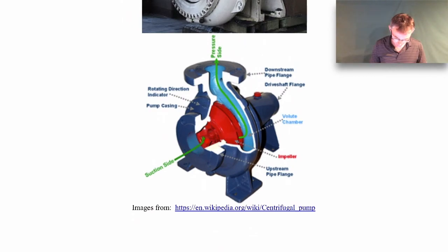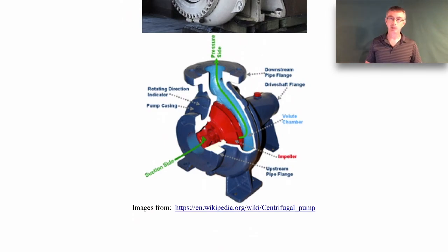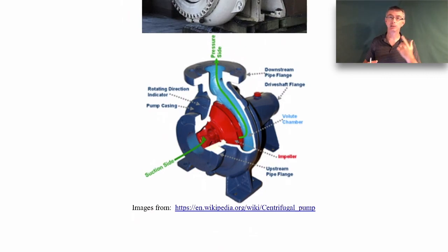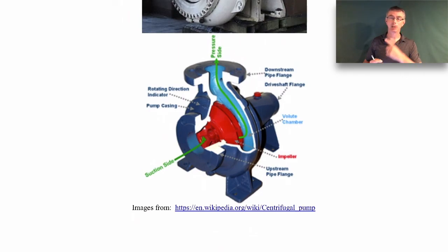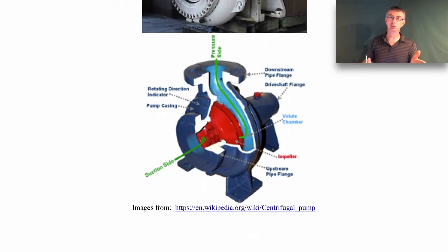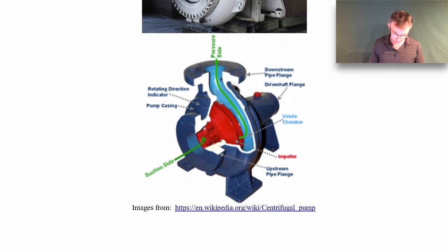The flow comes in with low pressure and goes into this spinning impeller — the red thing — and what it does is throw the fluid to the outside. If you're standing on a merry-go-round at some radius, from Newton's first law you want to go in a straight line, but because the merry-go-round is spinning it feels like you're being thrown out to the side. That's what's happening to the water here — the liquid gets thrown out through the edges of the impeller.